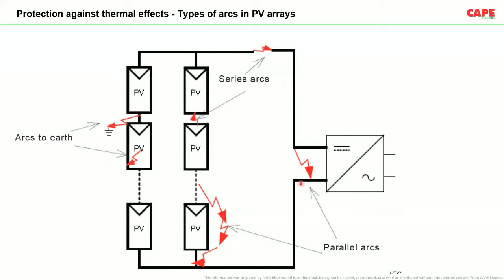Then the parallel arc. A parallel arc is the arc between two DC wires, like the positive and negative wires. But please note that against parallel arc, double insulation provides a certain amount of protection, because double insulation means even if one insulation goes off, there is one more insulation to protect the people. I will just show you what is written in the standard about this particular subject.